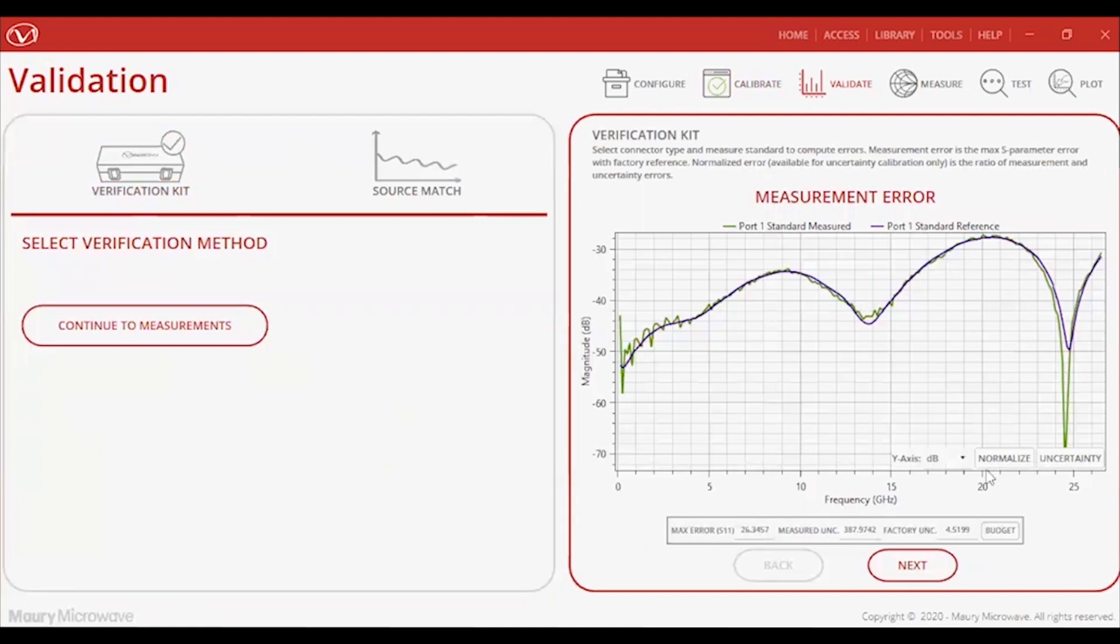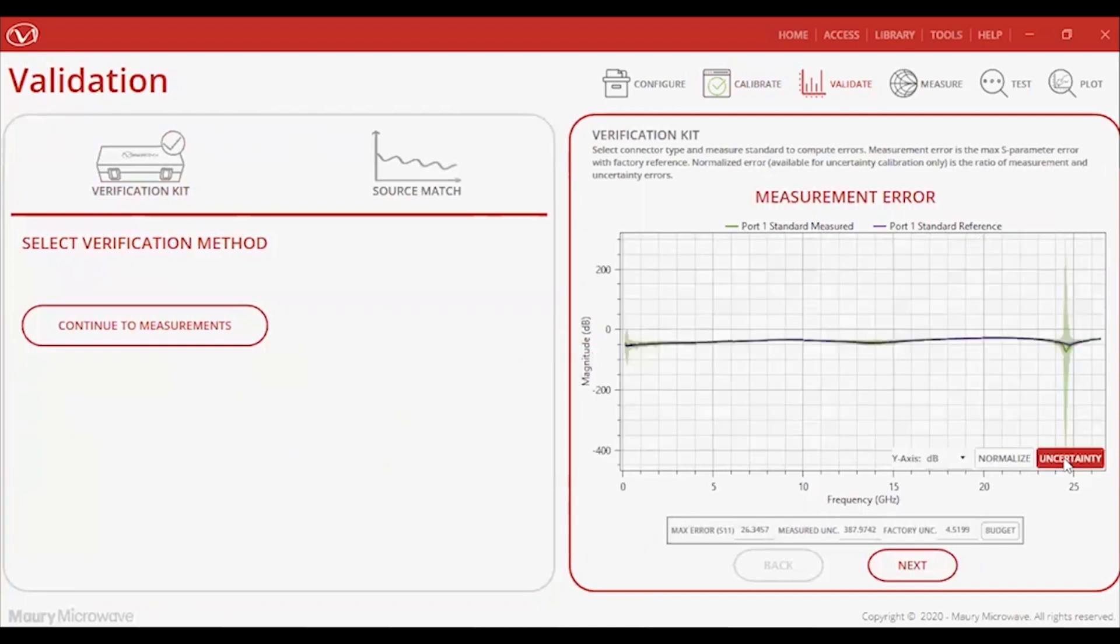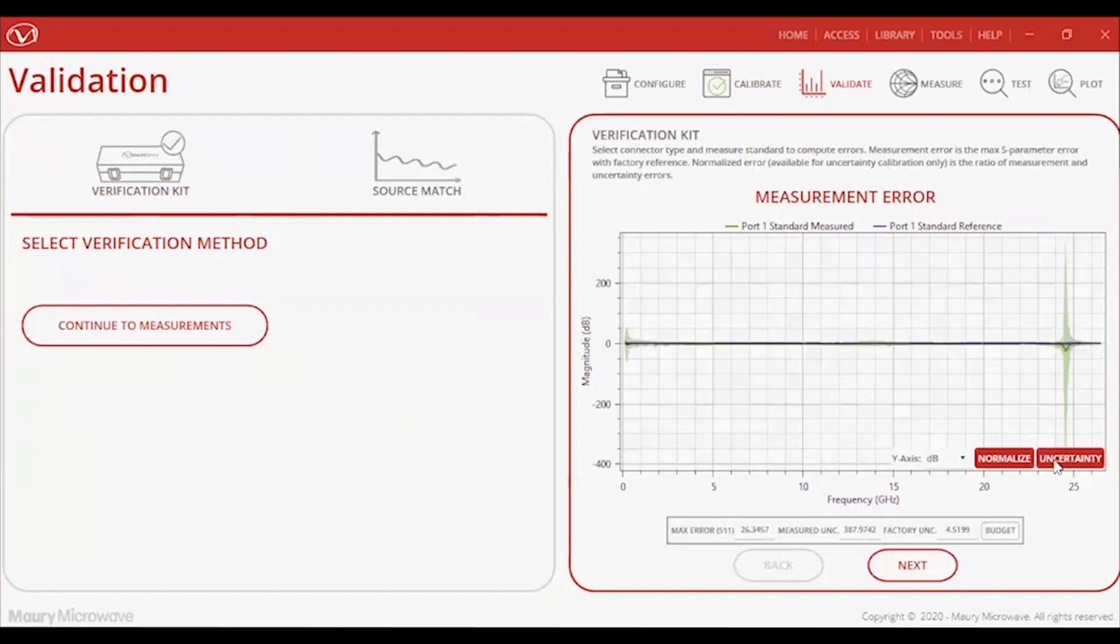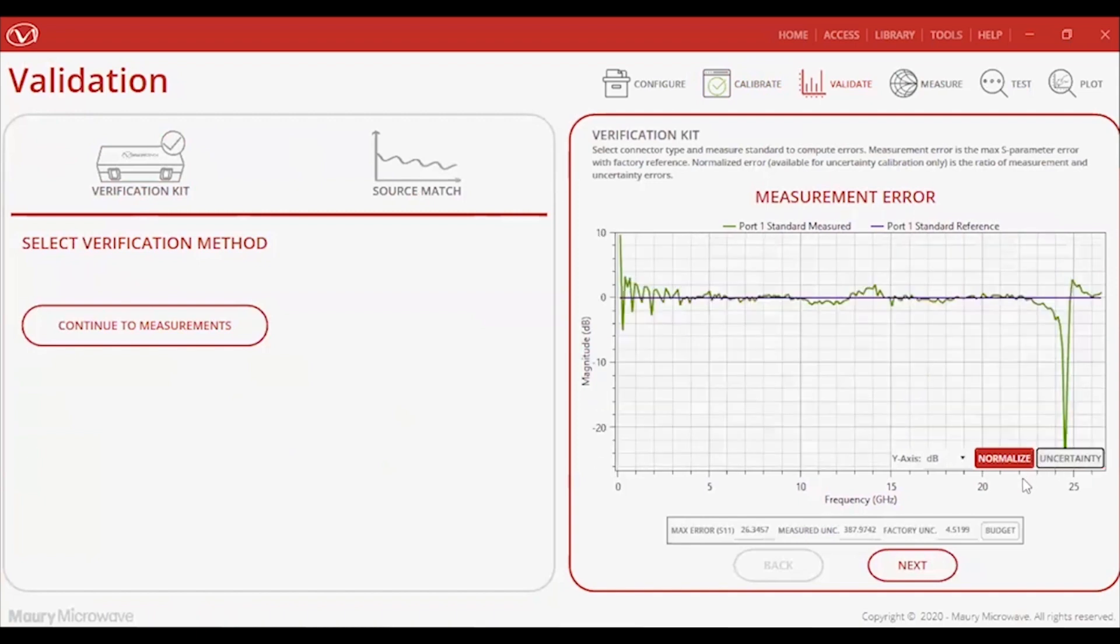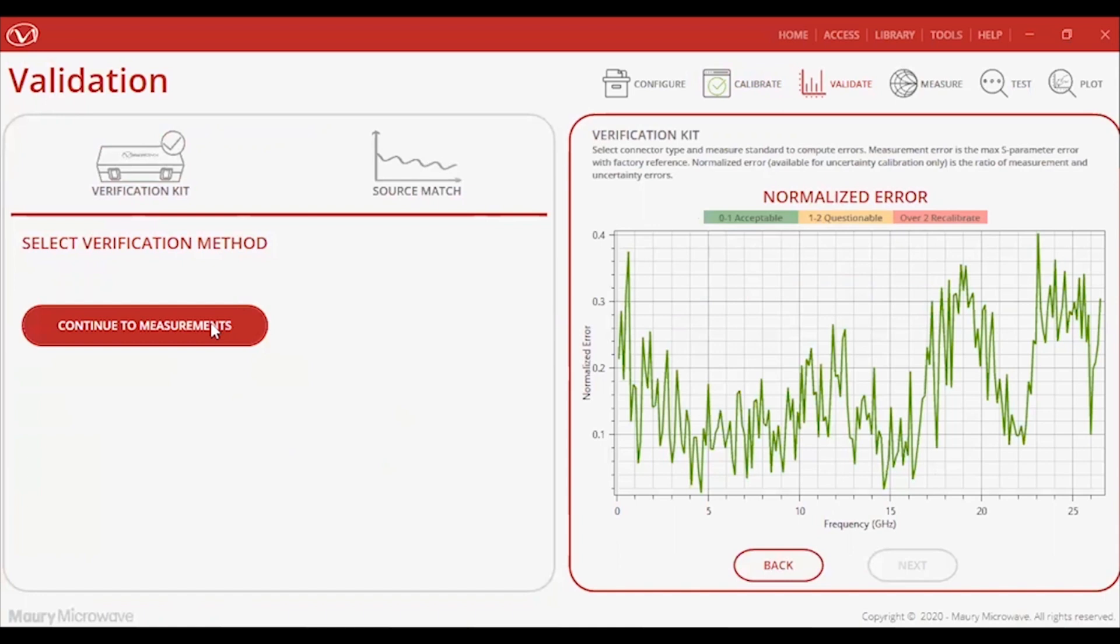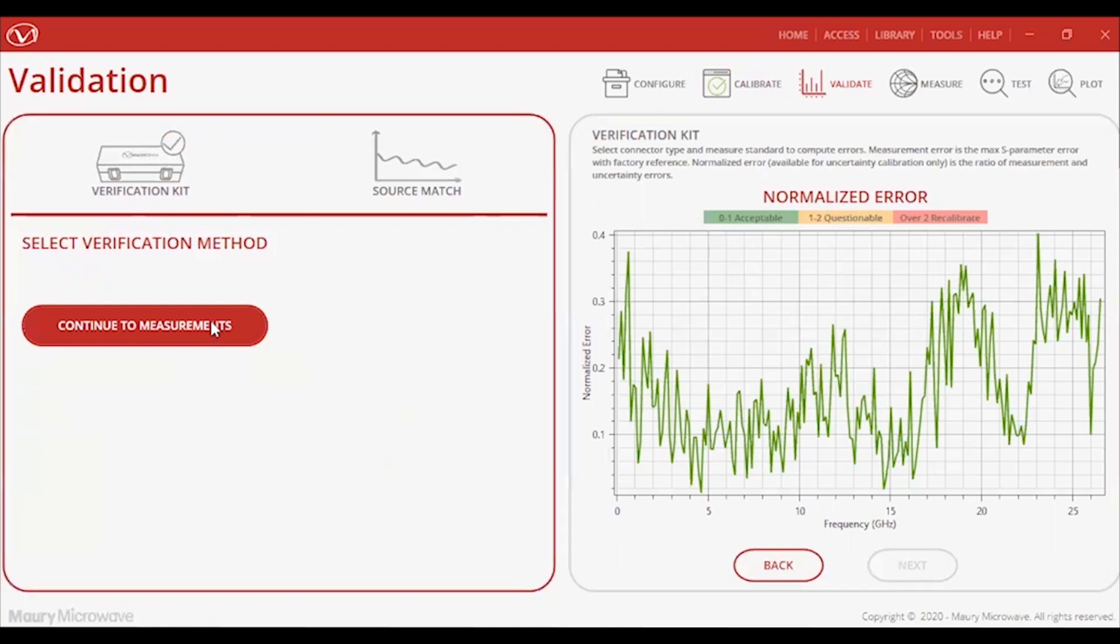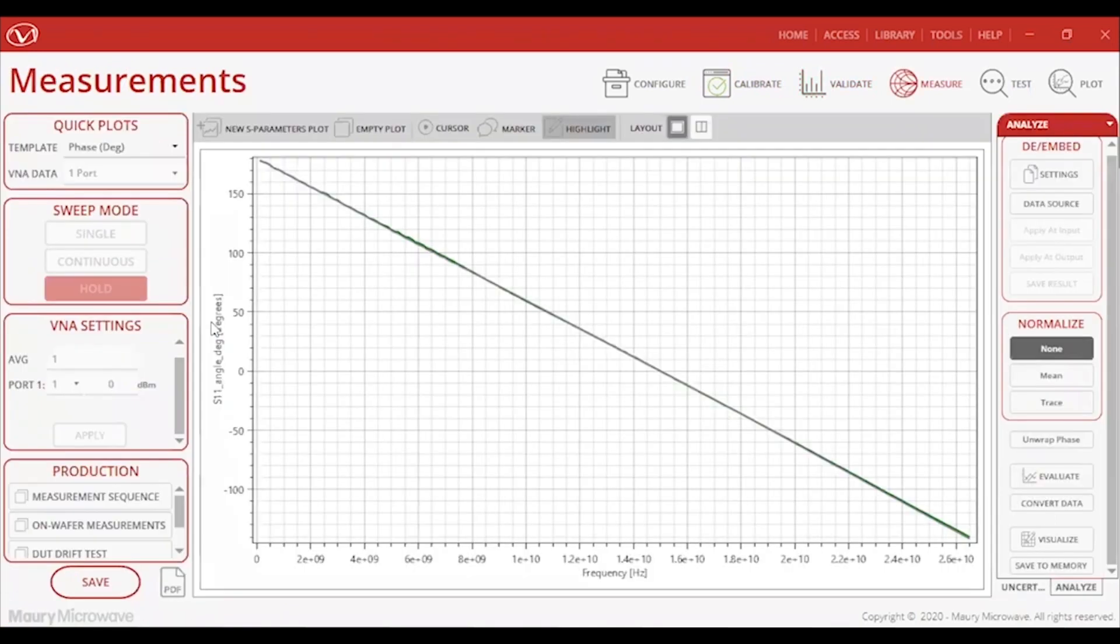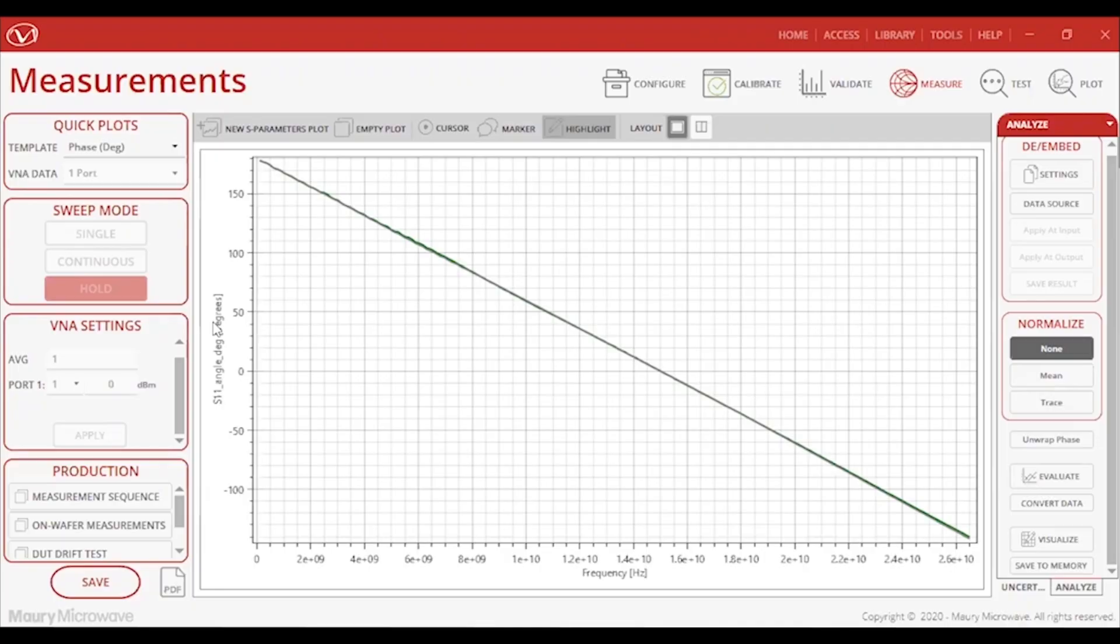I ended up choosing to go with the one-port verification load. I then measured and fetched the definition file of the load standard so that the data can be computed to show the measurement error in my calibration. This is where the benefit of having a characterized cal kit comes into play. The uncertainties included with the kit helps you decide if you need to calibrate again. This can now enable your 8510 to have a pass-fail criteria to enable the user to know how accurate their calibration is. Now that I'm done validating my calibration and have an idea of how accurate it is, I can move on to confidently taking measurements.